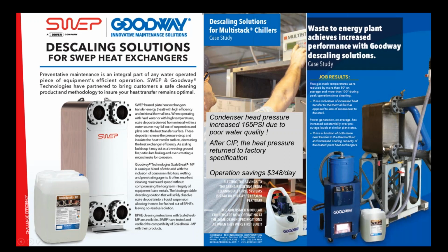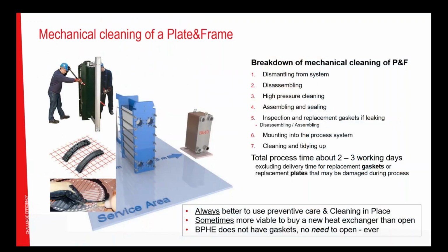The other example we have here is an installation of a heat recovery in a black water plant, a brazed plate installation where it's black water, it's poop, and even this system was cleaned out and returned to factory specifications. So with these two examples, I hope that you can see that cleaning in place is an efficient way to clean out for different types of application, HVAC and process, you can say, and compare that to having manpower opening up a system, having every plate taken out, cleaned, and changing the gaskets.